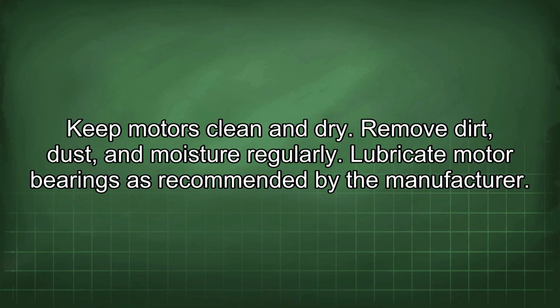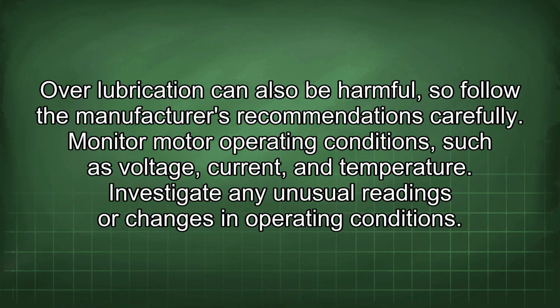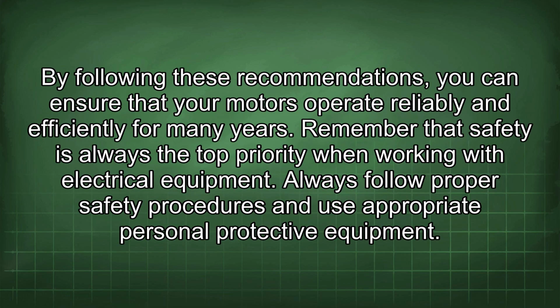Lubricate motor bearings as recommended by the manufacturer. Over-lubrication can also be harmful, so follow the manufacturer's recommendations carefully. Monitor motor operating conditions such as voltage, current, and temperature. Investigate any unusual readings or changes in operating conditions. By following these recommendations, you can ensure that your motors operate reliably and efficiently for many years.